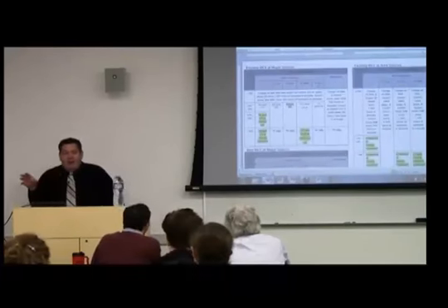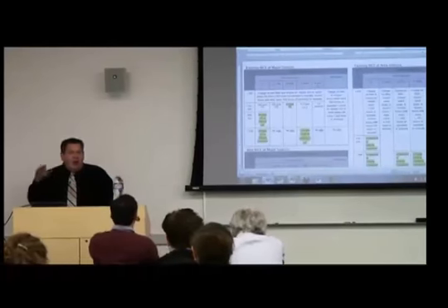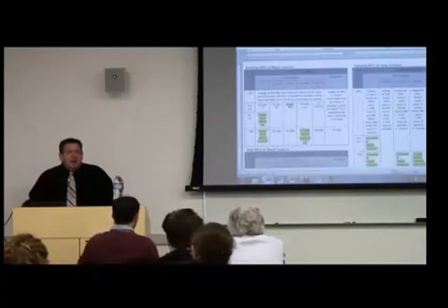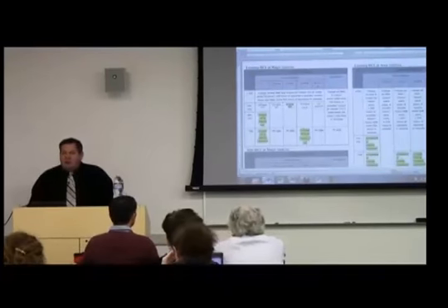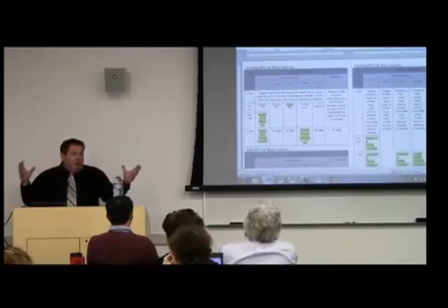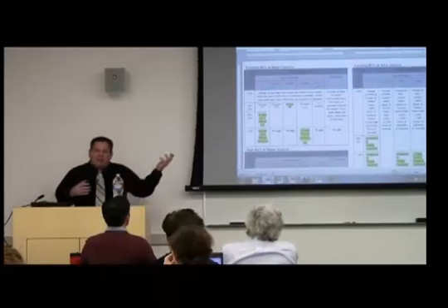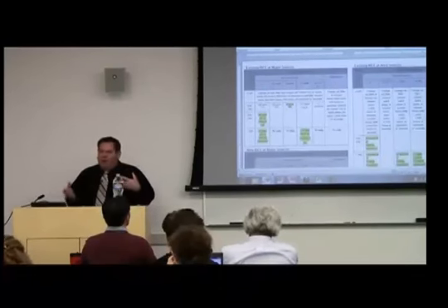Other engines either have work practice standards or what they call management practice standards, or they have operational limits. Other engines have numeric emission limits. Some of the engines on this cheat sheet with numeric emission limits are highlighted in yellow and some aren't. The ones highlighted in yellow are anticipated to require a control device, a catalyst of some kind. Although, with the exception of one group of engines, the regulation doesn't mandate catalyst. It just says you have to achieve these emission limits. And because they're lower than what the average are for all those engines, it's anticipated you'll need to add some type of control device.